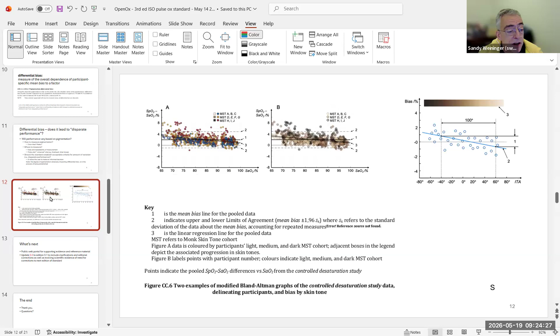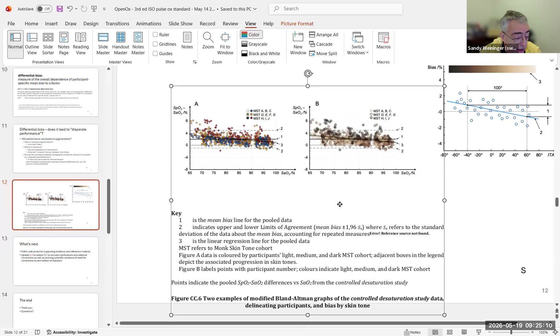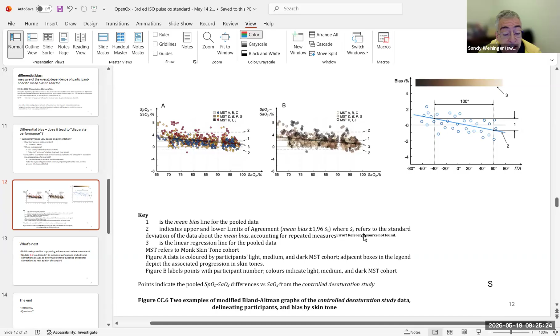So we tried not to abandon the manufacturers and the clinicians and people using it. The perspective of the standard is to try to give the tools to the stakeholders of the standard, the means to discern differences in performance, not to tell you what performance is acceptable for your particular clinical application, but to give you a comparable means for comparing Model A manufacturer to Model B manufacturer and trying to make some sense out of that. And so you can do procurement in an educated manner.